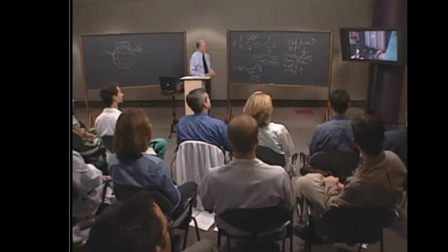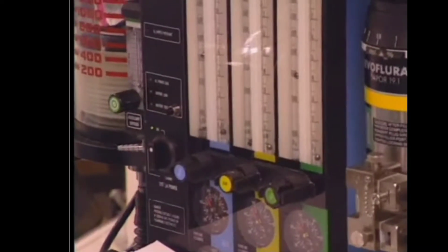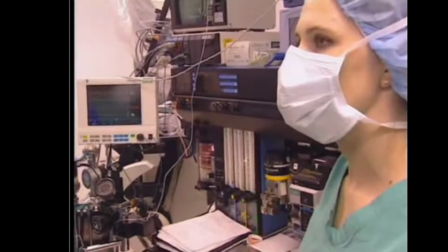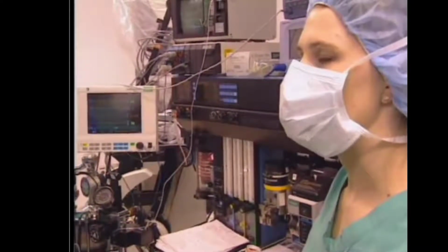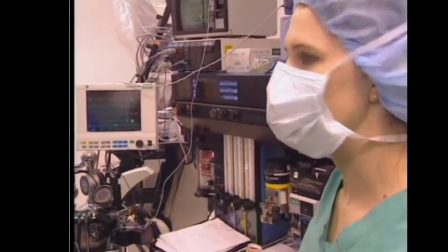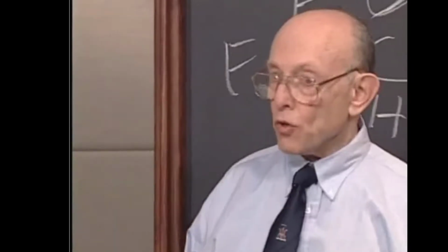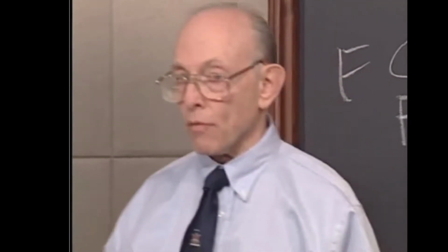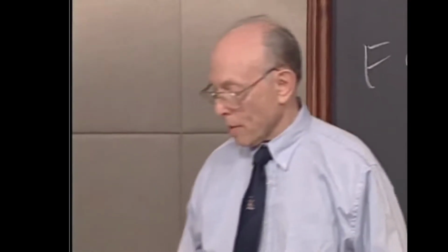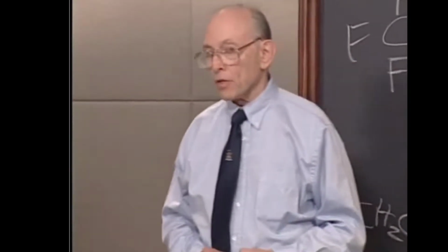Why don't you lower the flow rate to 300 and 300? So now our total flow is 600 cc's per minute. Is this permissible? No. The minimum flow for sevoflurane is 1 liter per minute, so we shouldn't go below that. Right. 1 liter per minute flow rate. Right. That covers what we need to do in terms of keeping safe and avoiding any problems with compound A.